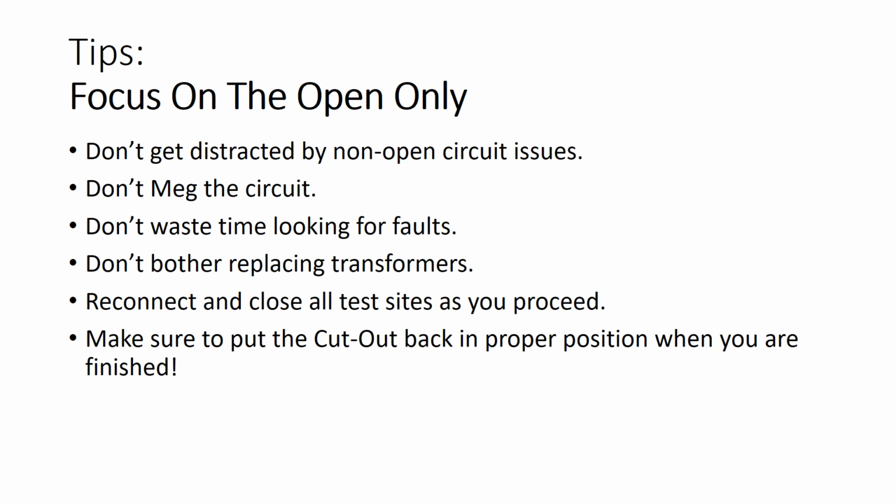So don't get distracted by non-open circuit issues. Don't Meg the circuit. That's not going to help with an open. Don't waste time looking for faults. And don't bother replacing transformers. A bad transformer does not create an open.